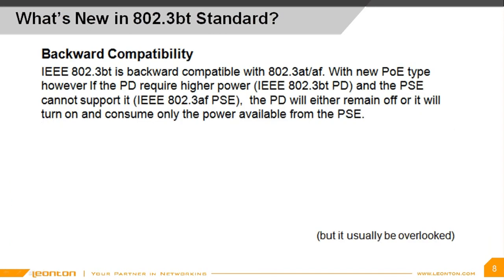The high-power PoE is fully backwards compatible with the previous PoE standard. A low PoE class device, such as a class 1 PD, can connect to a high PoE class device, such as a class 6 PSE, without any issues. However, in a scenario where a high PoE class device such as a class 6 PD is connected to a low PoE class device such as a class 4 PSE, the PD would either operate in a respective lower power state — called power demotion — or the PD will operate at its highest power state, causing the PSE to turn on and off. Both PSE and PD require the support of power demotion, but usually power demotion is not implemented due to additional costs.